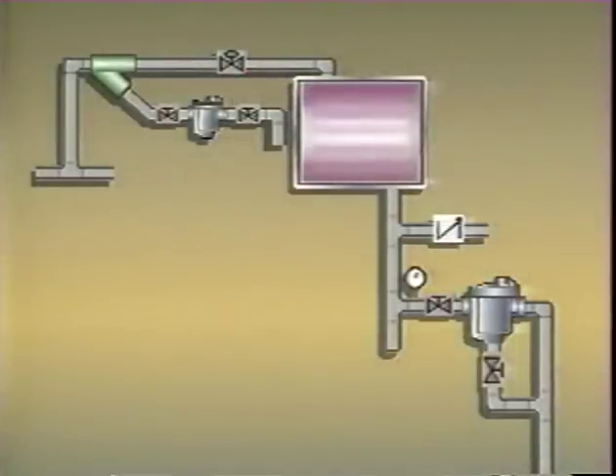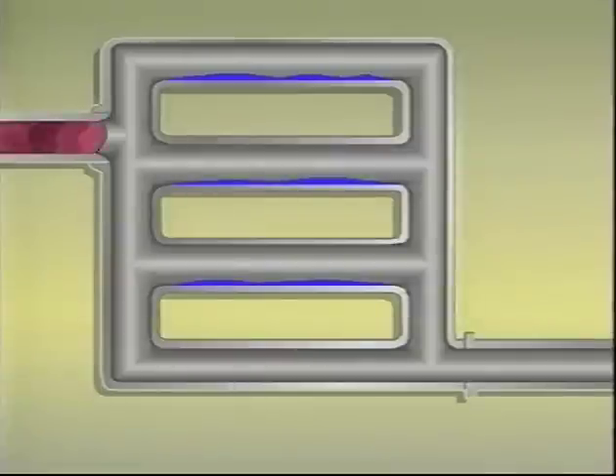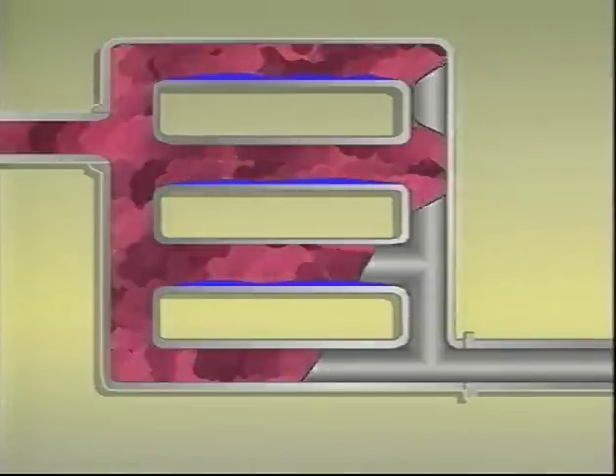Condensate controllers maintain a positive amount of differential pressure across the coil at all times. All the tubes will be fed from the supply end only, preventing the entrapment of steam and the resulting thermal shock.